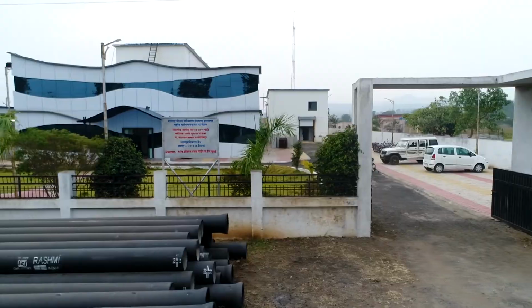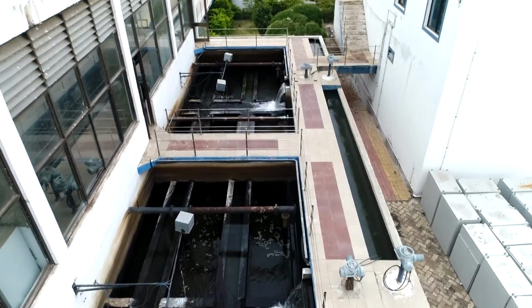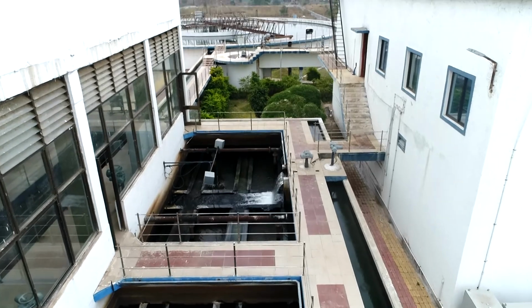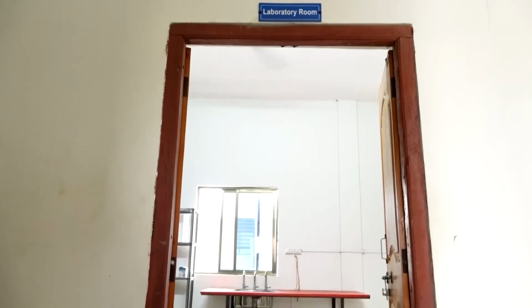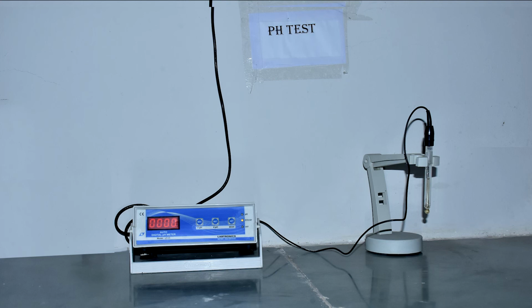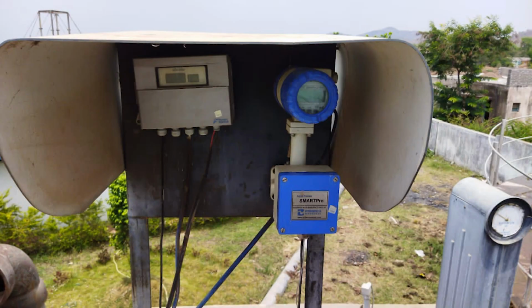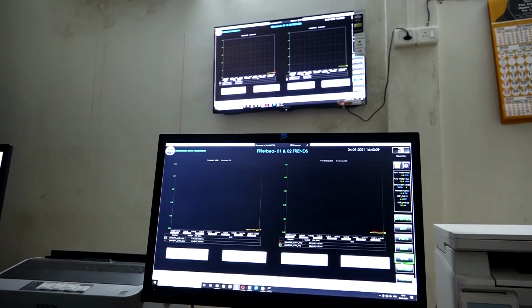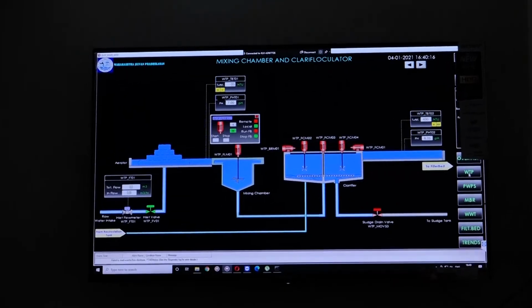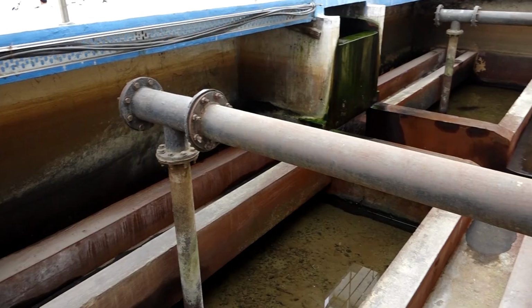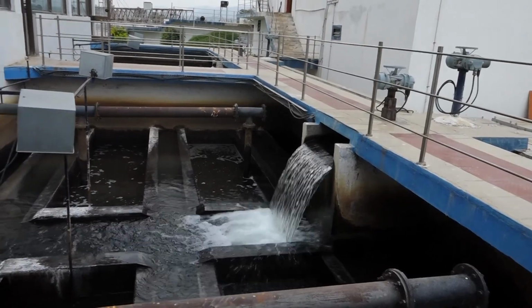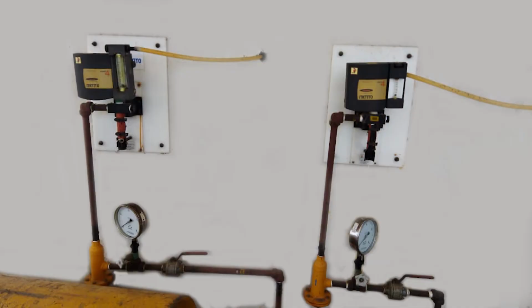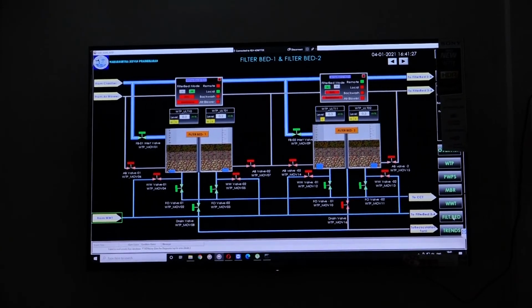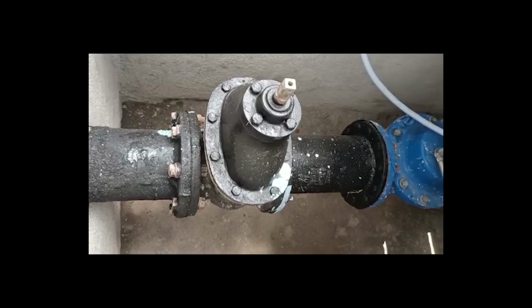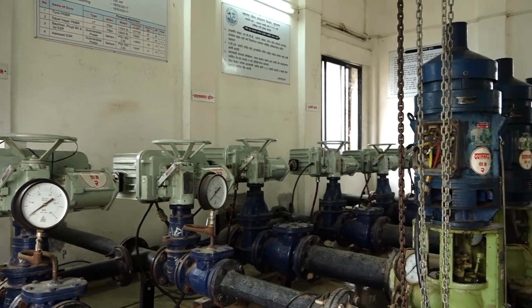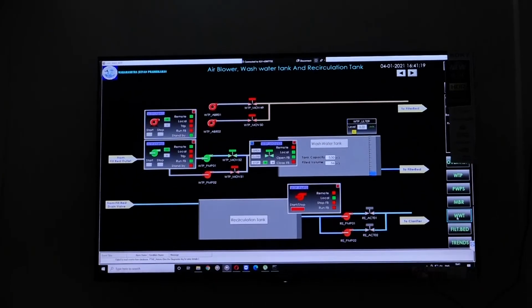A water treatment plant of 31 million litres per day capacity was constructed with the advanced feature of PLC and SCADA-based operations. All the quality parameters of water such as pH, turbidity and chlorine content are sensed and monitored through the SCADA system automatically. The operation of the flash mixer, clariflocculator, backwashing, cleaning of filter beds, wash water recirculation and chemical dosing is automatically managed through the SCADA system by using the appropriate logic as per the process requirements. All valve actuators, pumps and air blowers are controlled and operated through the SCADA system.